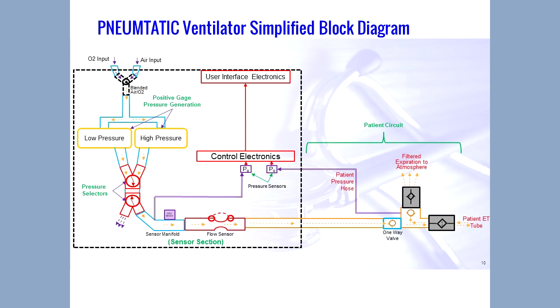You have pressurized oxygen and air, and it's coming into two different pressure chambers, one we call the low pressure and the high pressure. The high pressure is for inhaling, at the peak inspiratory pressure that needs to be set with a knob on the top of the ventilator. And the low pressure is the positive end expiratory pressure. That's when you exhale, what that end pressure is to the lungs. And those two have to be managed.